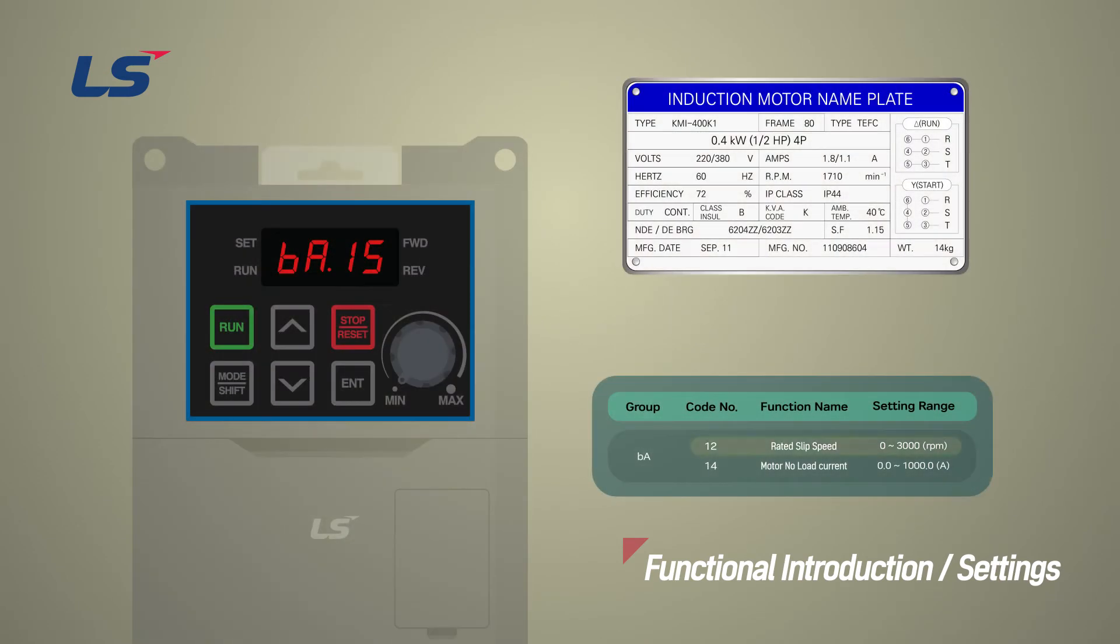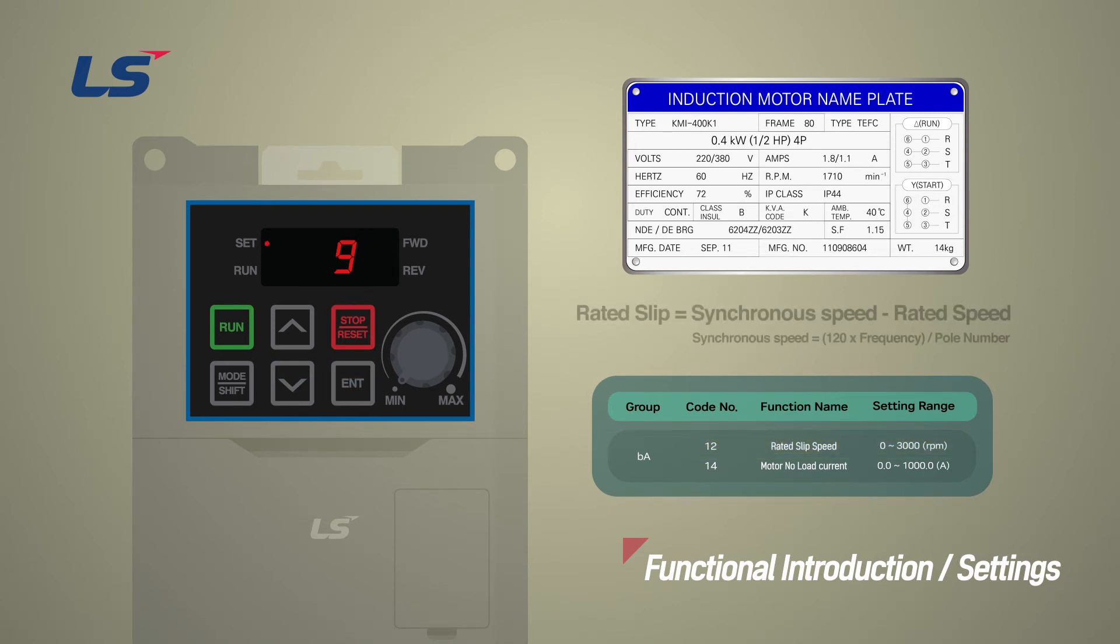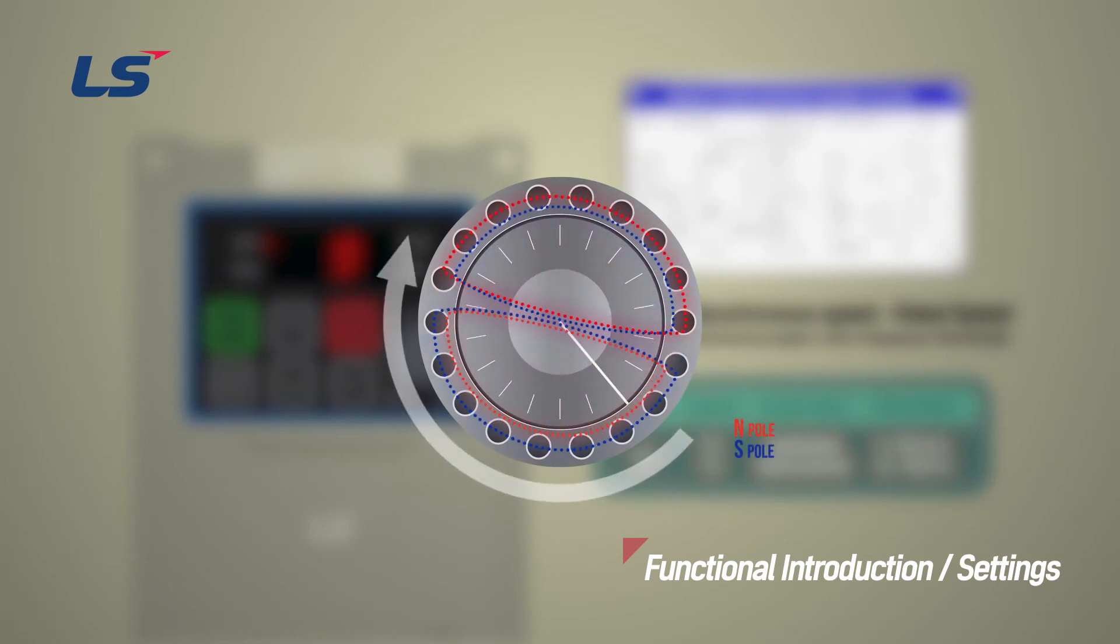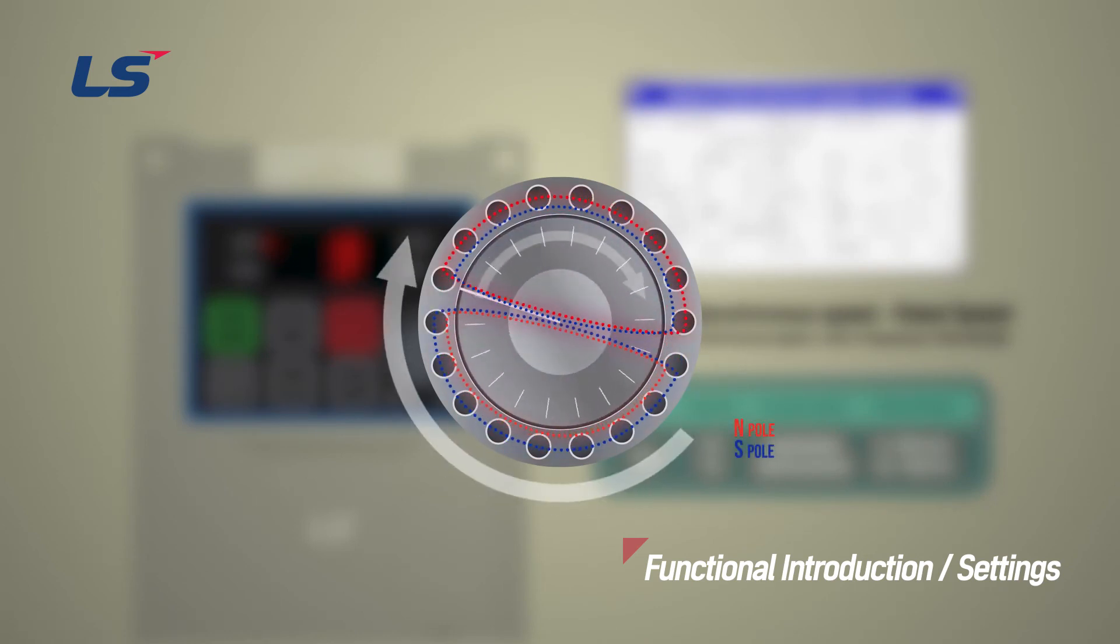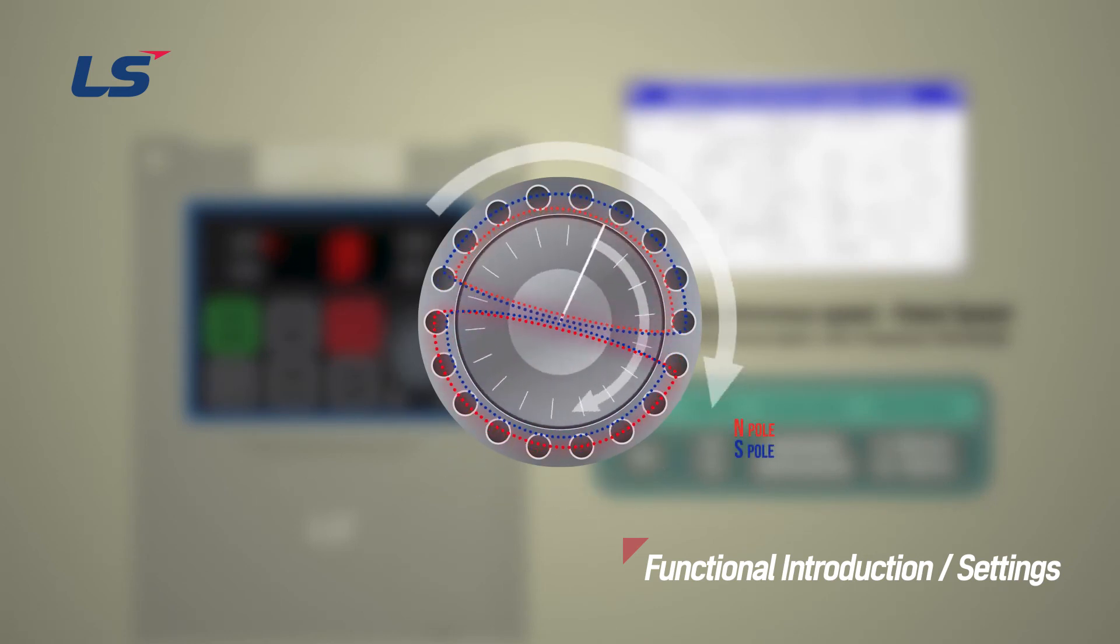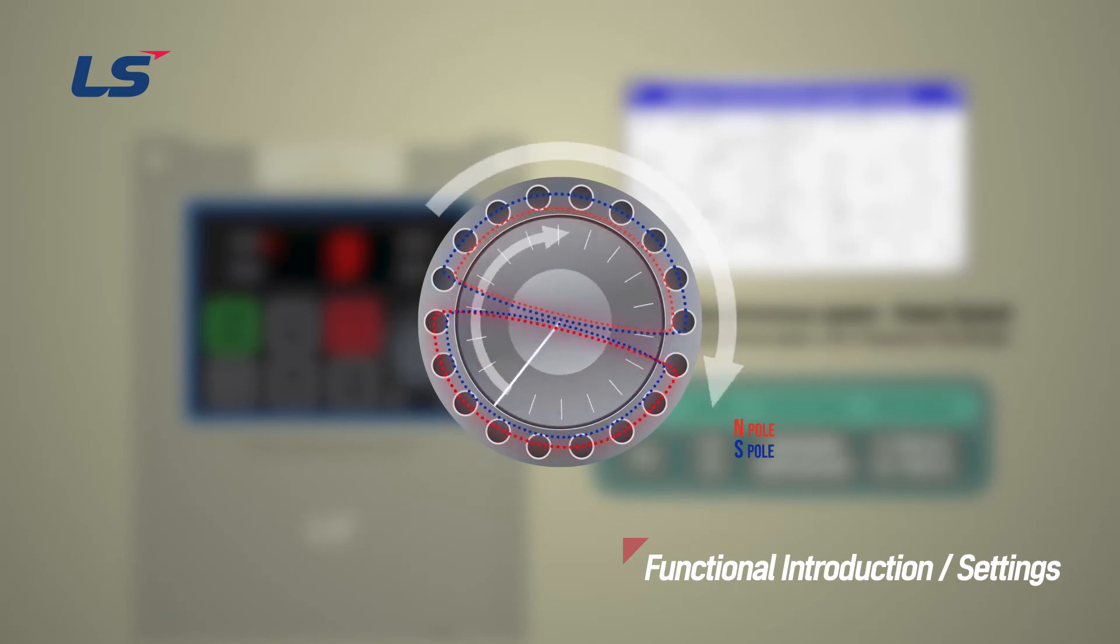The rated slip of the motor can be entered in BA12. The rated slip means the difference between the synchronous speed and the rated speed. When induction motor creates a rotating magnetic field, the rotor rotates along with the rotating magnetic field.